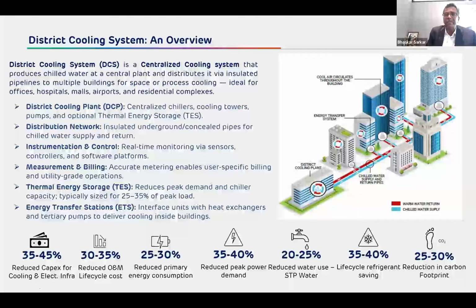That is first. Second, this refrigerant is used in machines which are in a separate cooling plant, which is carefully monitored through leak detection systems and advanced SCADA systems. So there is zero leakage. On the other hand, if we go to any conventional system, we are very much used to the term refrigerant leak, gas leak.